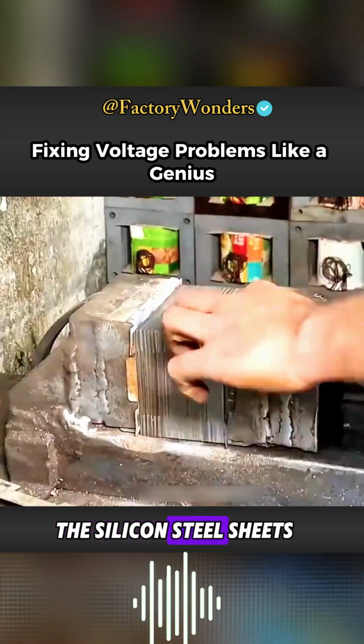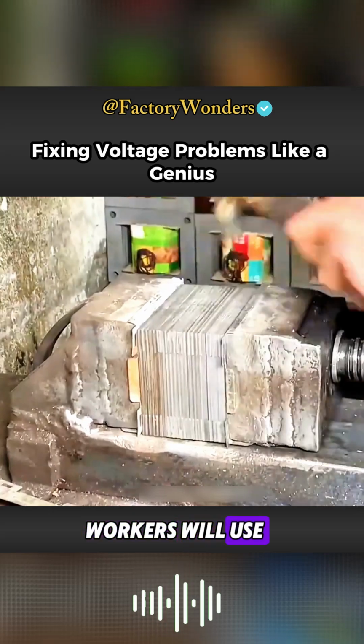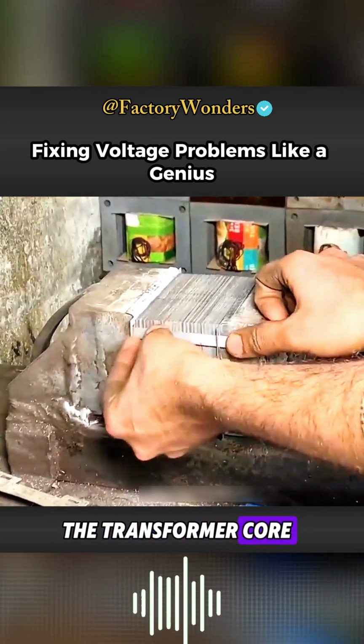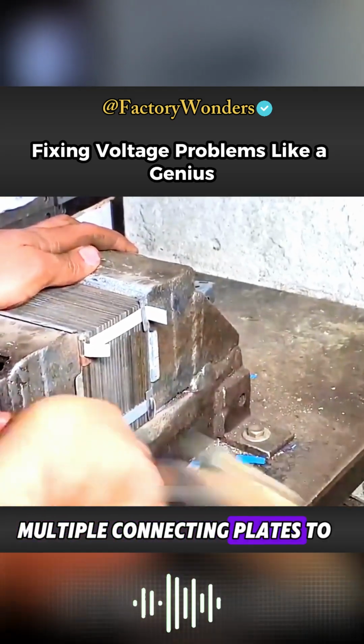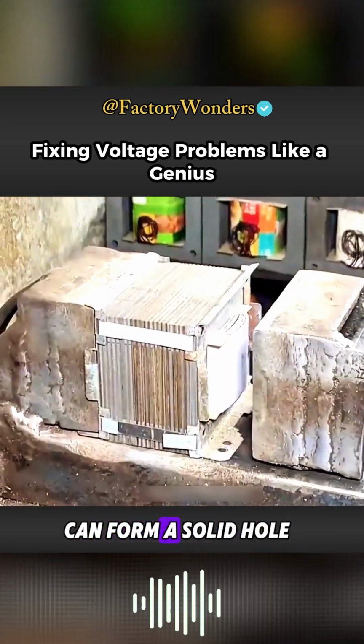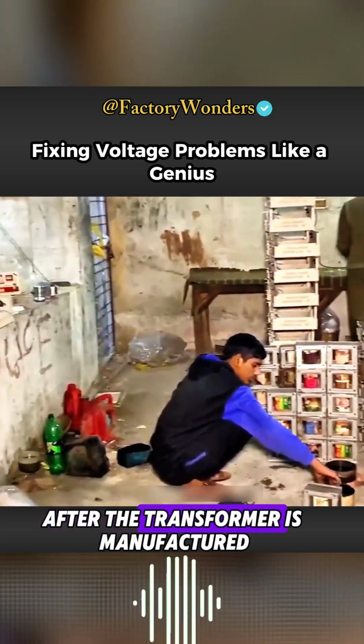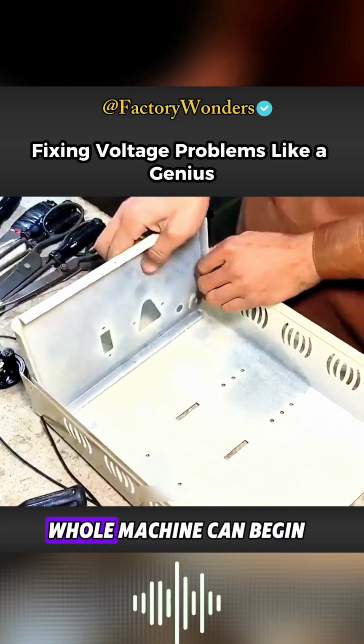Next, the silicon steel sheets need to be tightened. Workers will use two brackets to tighten the transformer core and then use multiple connecting plates to tighten the brackets at both ends to fix them. In this way, it can form a solid whole. After the transformer is manufactured, the assembly of the whole machine can begin.